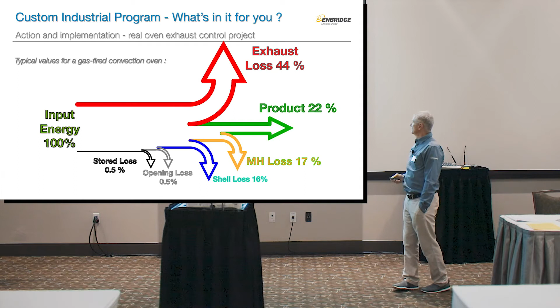44% goes into exhaust. So if you look at it that way, this becomes a completely different business case. Because that little puff is actually 44% of your energy. Half. And that's typical. I've seen people who have 65%. So this is not an outlier, this is average. So what we've done on one of them, we actually helped them install not only the fan that took the cold air, put it through the heat exchanger, through which exhaust then heated the incoming air, but we also reduced that exhaust volume as well.